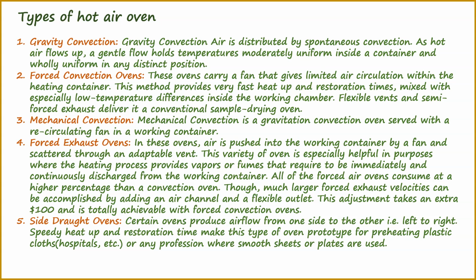Mechanical convection. The third type of oven is mechanical convection. It is a gravity convection oven served with a recirculating fan in a working container. This fan helps to maintain a consistent temperature throughout the oven.